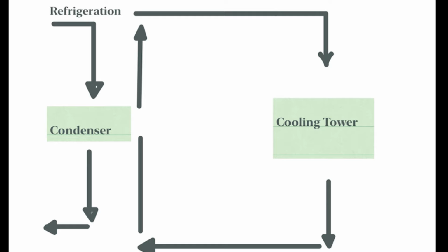Differing from the 2 cycles above, this is an open loop cycle, where non-potable water that was warmed by refrigerant goes to the cooling tower, where heat evaporates into the atmosphere, and the condenser water is cooled and goes back into the chiller.